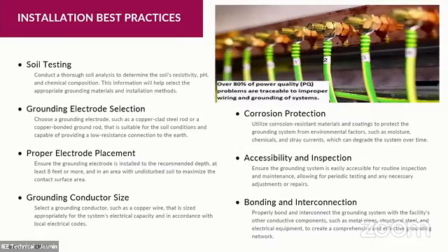Grounding conductor size, as mentioned, is referred to the Philippine Electrical Code. For grounding equipment, our basis comes from the Philippine Electrical Code, and the basis is the size of the OCPD. When it comes to system grounding, we consider the size of the grounding from the largest size of the conductor.